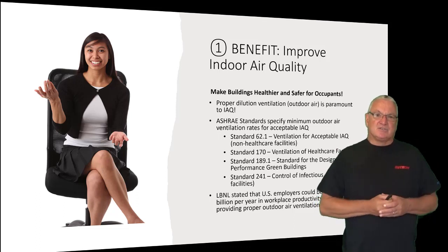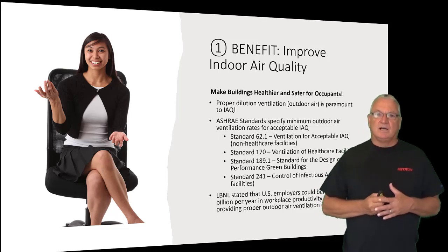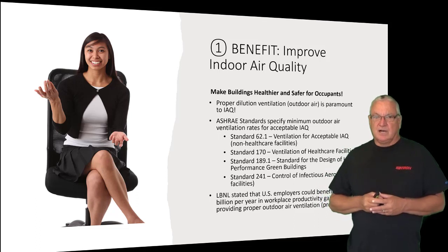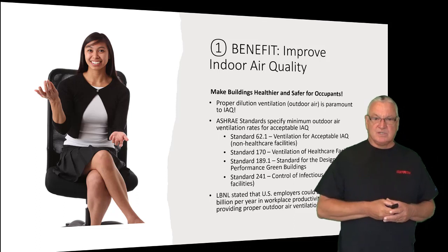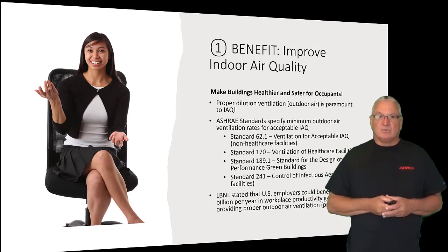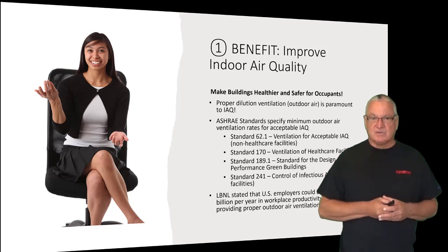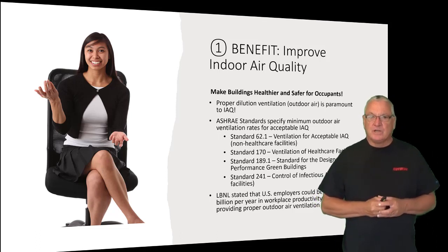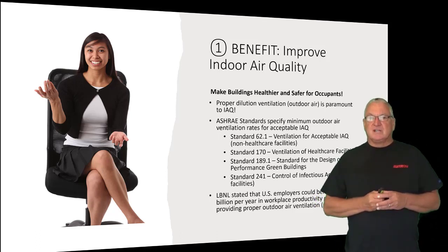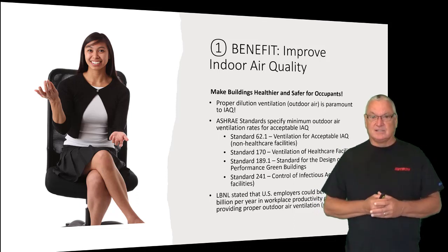If you look at the industry, there are a number of standards that all specify these ventilation rates. We have standard 62.1, which is ventilation for acceptable IAQ in non-healthcare facilities. For healthcare facilities, we have standard 170. We also have standard 189.1, which is the standard for the design of high-performance green buildings, which is also the IGCC. And recently, we have standard 241, which is control of infectious aerosols, which I think is really important, and I'm pleased to see that ASHRAE has actually done something there.